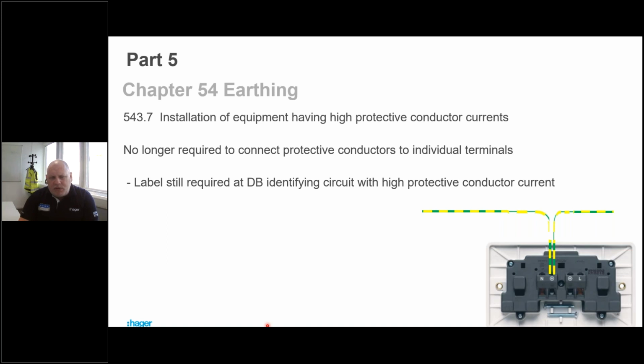But in the board, we've still got to stagger our earths where we've got this high protective conductor current. We still have to put a label inside the board to say that's what we've done. So just be aware of that. You can use the sockets now with a single point, but in the board, you would still split up your earthing arrangement.